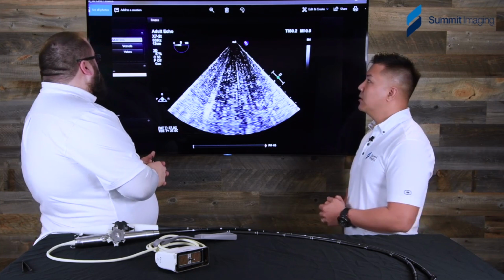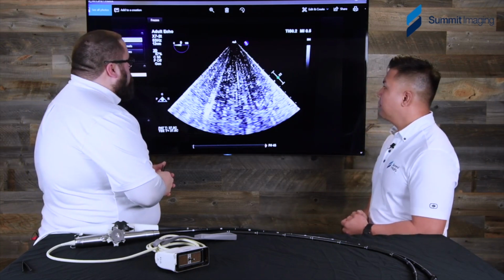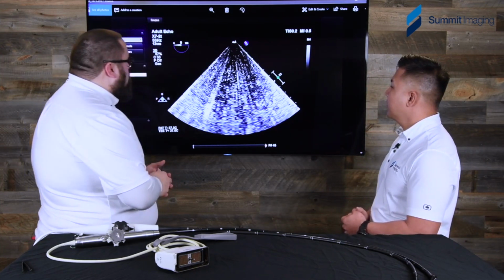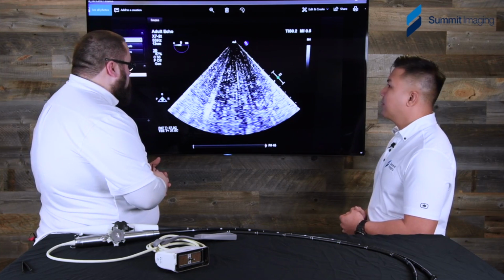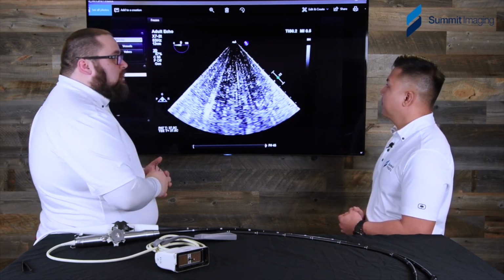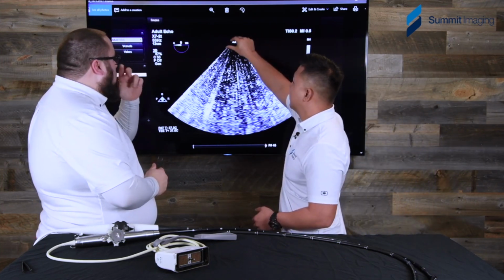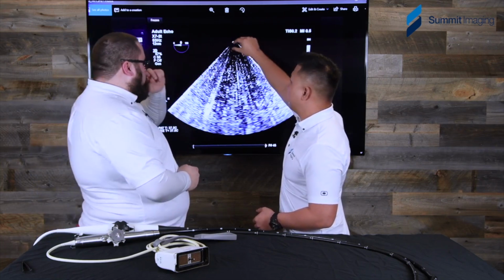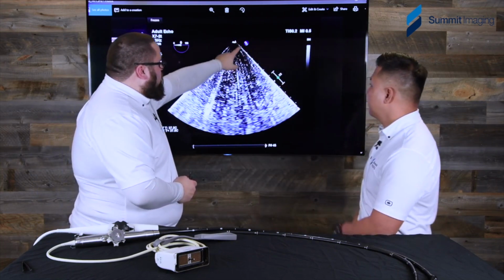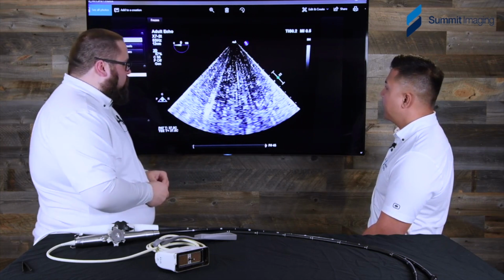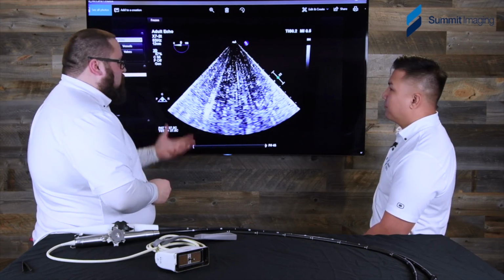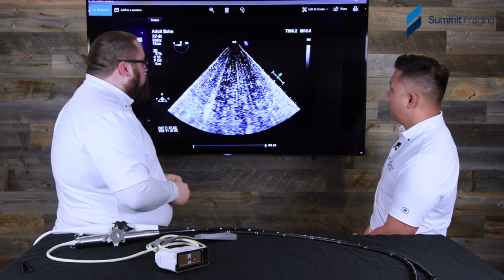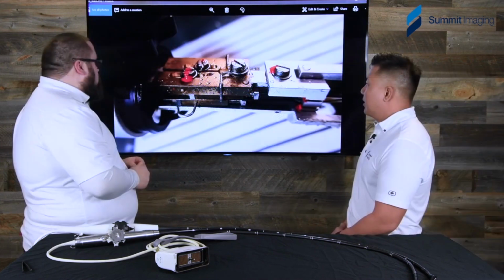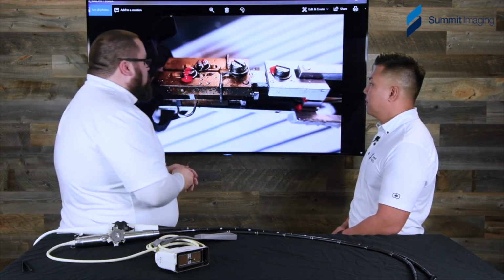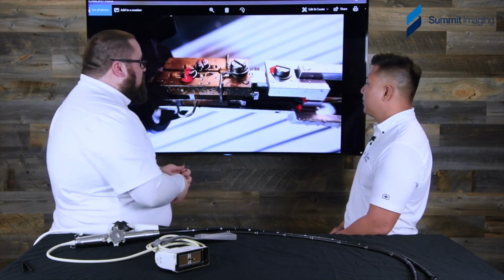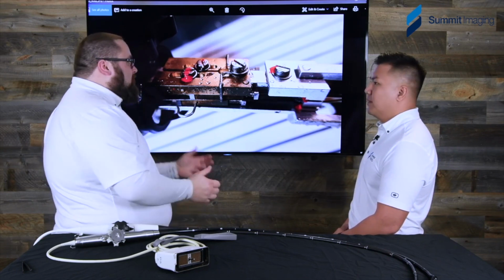Well, looking at this transducer too, the lens appears to not be showing up properly in the image as well. It's gone. You should see at least a raw band up here, and it's gone now. And you should have the little tulip. It's not even seeing basically its own lens in the image. Exactly. This is a pretty extreme example of maybe a wet hand grabbing the handle. More likely, it probably slipped into the sink.